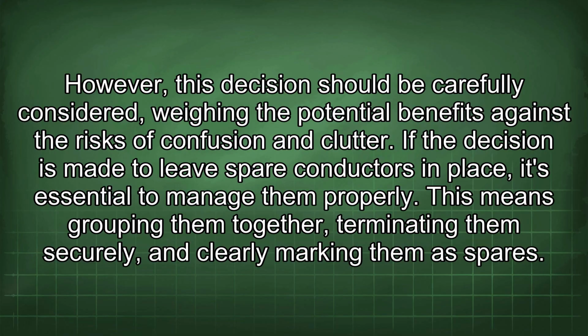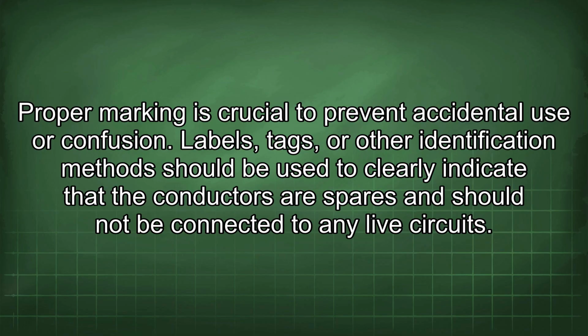If the decision is made to leave spare conductors in place, it's essential to manage them properly. This means grouping them together, terminating them securely, and clearly marking them as spares. Proper marking is crucial to prevent accidental use or confusion. Labels, tags, or other identification methods should be used to clearly indicate that the conductors are spares and should not be connected to any live circuits.